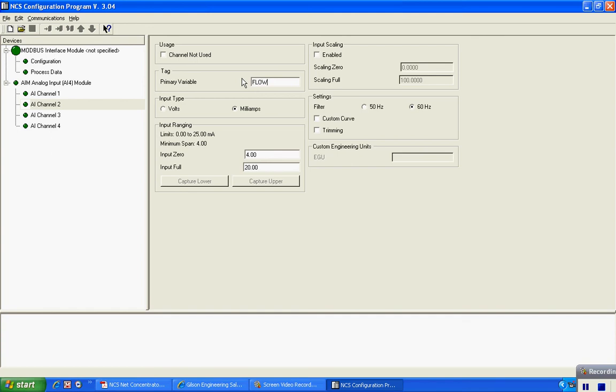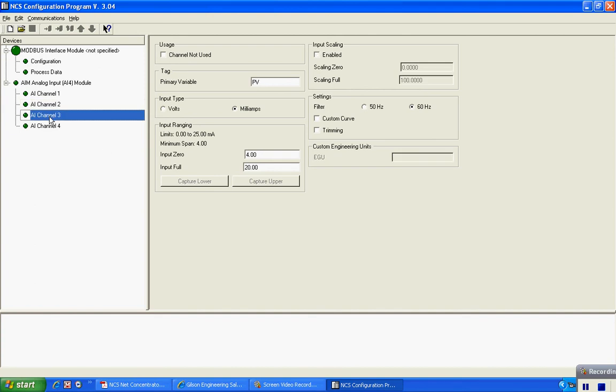I can do this for each of the inputs that are available on this input module. This second one we'll call flow. It's also a 4 to 20 milliamp transmitter, and in this case it's a 0 to 200 GPM signal. I'll put 200, put my engineering units here of GPM, and I can do this for each of the inputs that are available.